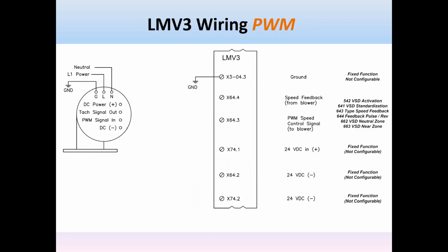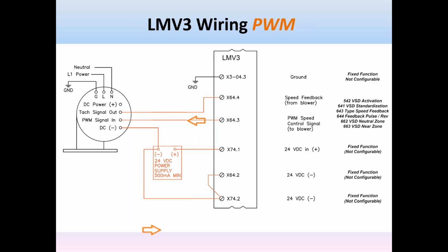The other air input option is a PWM, pulse width modulation. On the left, we see a typical pulse width modulation motor. 120 volts is presented to the motor at all times. And then you see the terminals for the control signals. LMV3 is again in the middle, and the description's on the right. You'll have to provide a power supply, 24 volt DC, to the LMV3 so that the LMV3 can generate an output PWM signal to control the speed of the motor. Additionally, that would power the board on there so that you can take an input back to the LMV3 from the tachometer. So again, like the VFD, we can monitor the speed of the air device for the combustion curve.